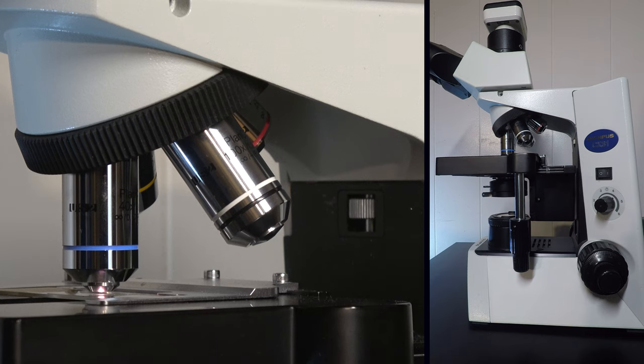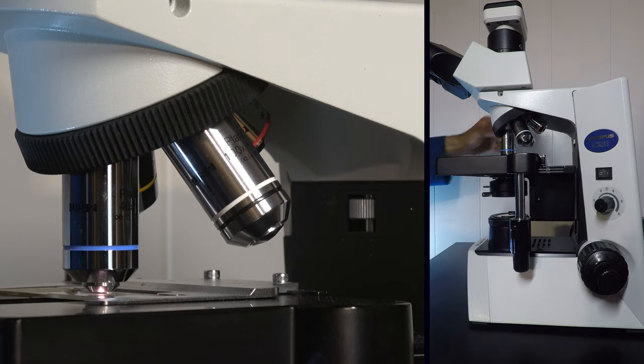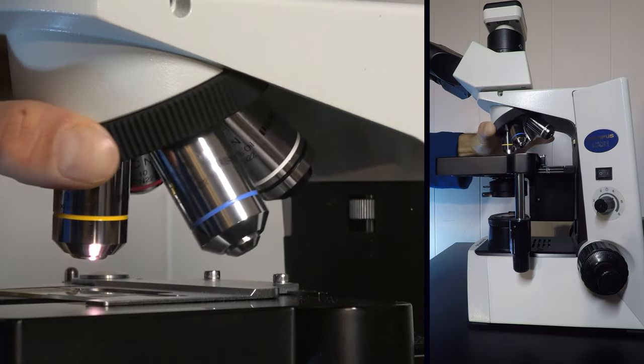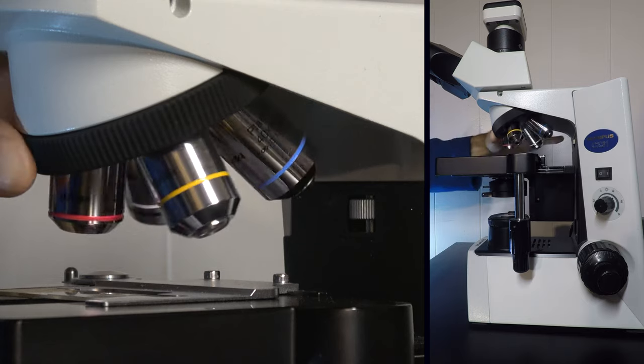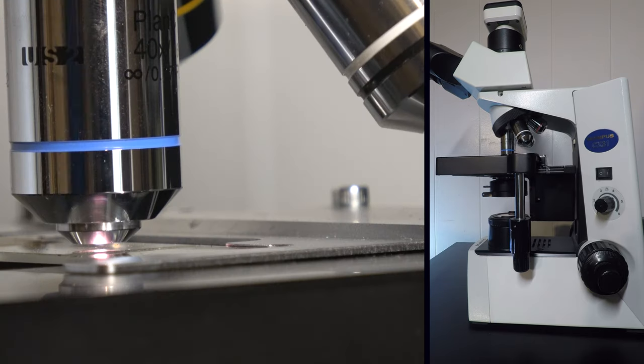Now if you are only going to use the 40x objective, then the proper way to return to the 4x is by going through the 10x. You only want to rotate to the 100x lens if you plan on using it.